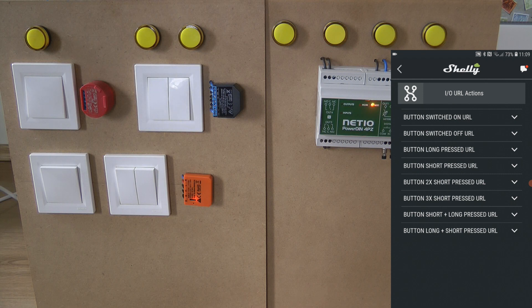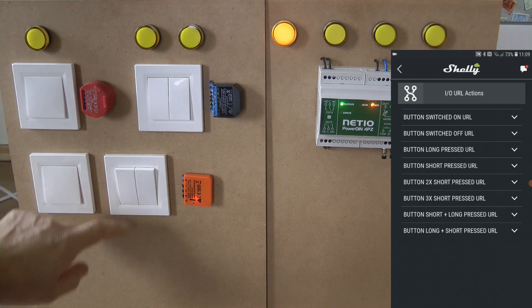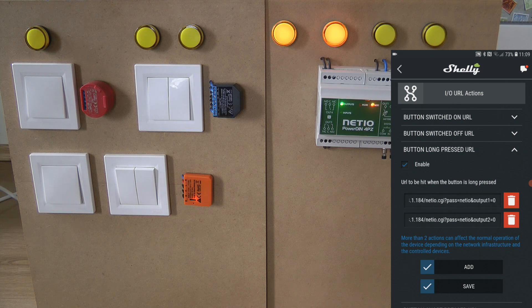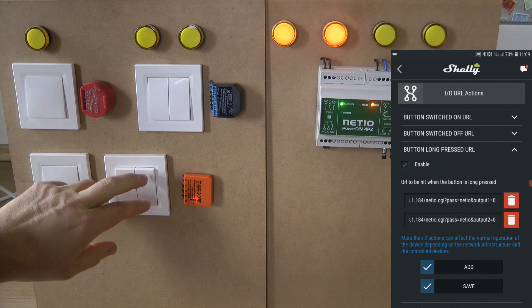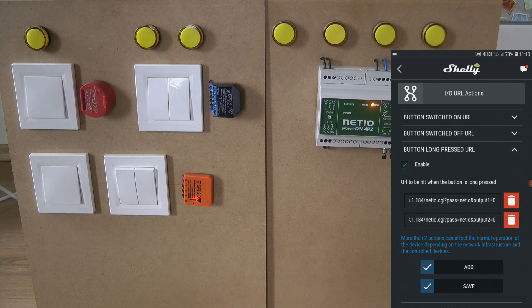I also configured a long press action, using the add button to add a second URL. On long press, the first URL turns off output one and the second URL turns off output two. So with a single long press on this button, both outputs turn off. You can use one action to instruct multiple outputs of the PowerDin to do something — in this case, turn them all off.